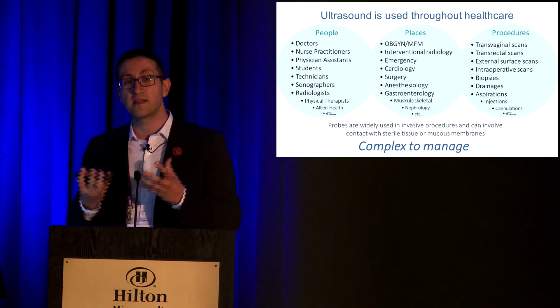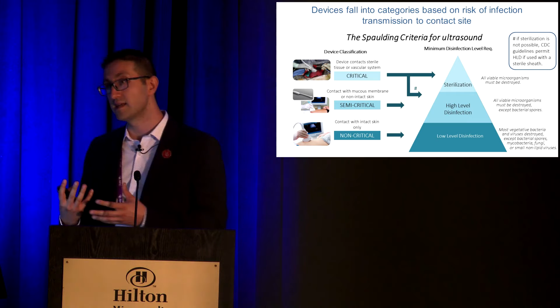And we always refer back to the Spaulding classification. So, obviously, if we are scanning intact skin surface area, then it is considered low-level disinfection or non-critical. If you're using it in contact with mucous membranes, then it is high-level disinfection, semi-critical. And if it's touching sterile tissue or the vascular system, then it is considered critical, and therefore sterilization would be required.